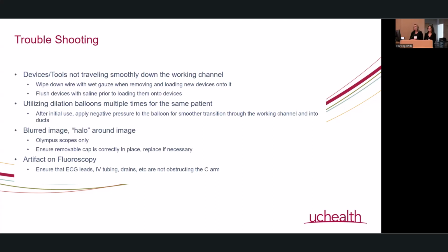And then on your dilation balloons, once you have dilated a patient, whenever you bring the balloon out, we do apply negative pressure, because that'll allow for a smoother transition to go back into the working channel and back into the ducts. Sometimes when you deflate the device, it'll still have a little bit of enlargement to it. So doing that negative pressure actually will help a ton.